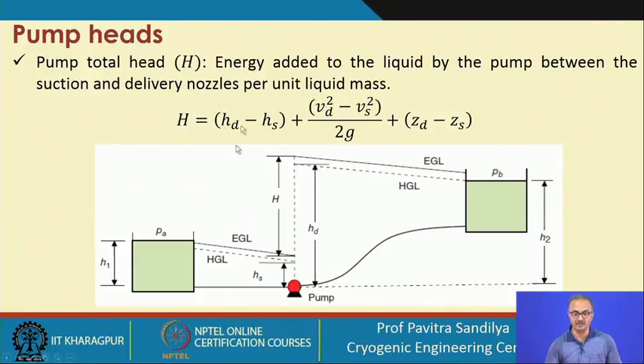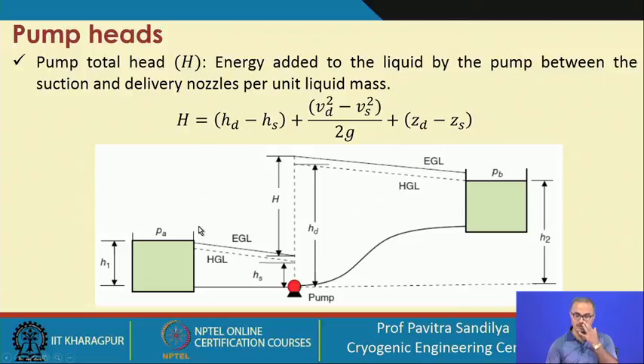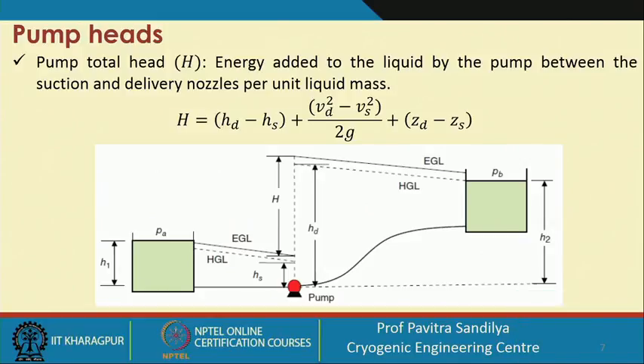The total head means the energy added to the liquid by the pump between the suction and the delivery nozzles per unit liquid mass — how much energy needs to be added to make the liquid flow from one pressure level to another. We can identify the potential head difference, the kinetic head difference, and the elevation head difference. Note that frictional head is neglected here as it is assumed to be similar on both sides.